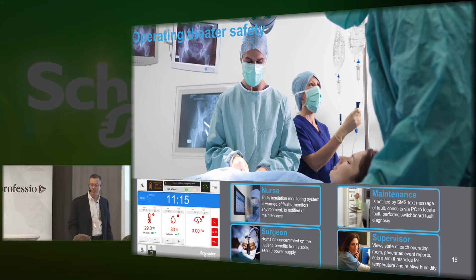To have your facility staff automatically notified, so they're working on it, so they don't have to think about it. They don't have to make the telephone call, so that the surgeon and the maintenance can take care of that, and the nursing station automatically knows what's going on in that power failure. But at the same time, the same system is used for other things to change the status of medical gases, what is the temperature, what is the pressure, what is the humidity, and enabling the staff to easily change that with a touch screen.